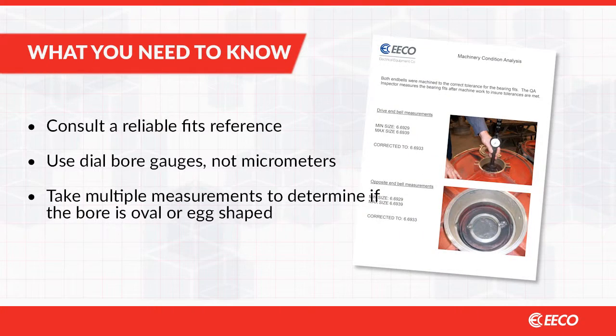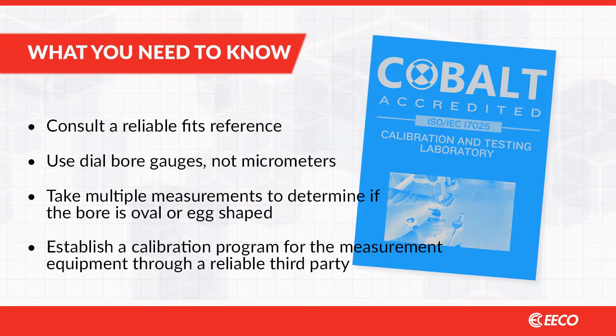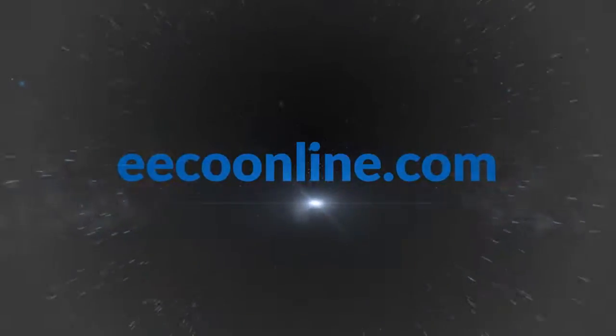Consult a reliable fits reference like those from SKF. Use dial bore gauges, not micrometers. Take multiple measurements to determine if the bore is oval or egg-shaped, and establish a calibration program for the measurement equipment through a reliable third party. If you have questions about this or any other topic, contact us at eecoonline.com.